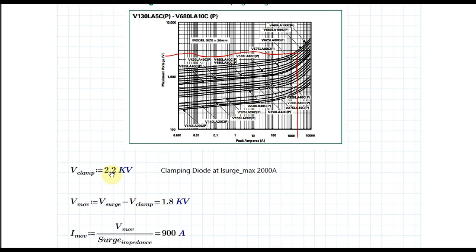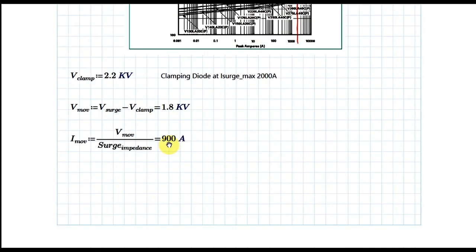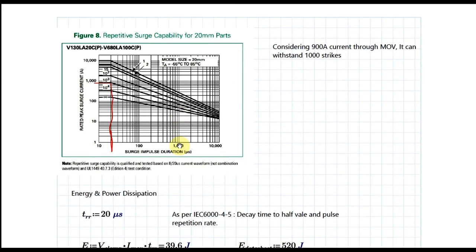For 2000 A, your maximum clamping voltage is approximately 2.2 kV, or 2200 V. The voltage across the MOV is: V_MOV = V_surge − V_clamp = 4 kV − 2.2 kV = 1.8 kV. The current through the MOV is: I_MOV = V_MOV / Z_surge = 1.8 kV / 2 Ω = 900 A.